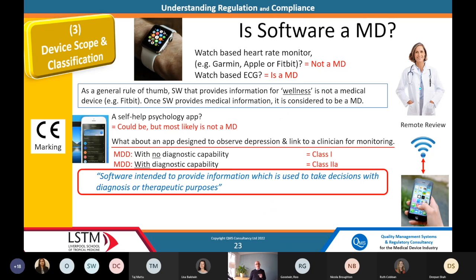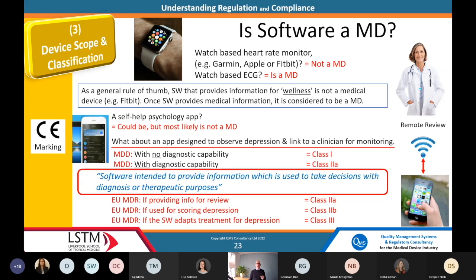Because of this new definition in the regulation, software intended to provide information which is used to take decisions with diagnosis or therapeutic purposes. Under the EU MDR, then software that was observing depression would be a Class 2A if it was being used for reviewing the depression. If it was being used to score the depression, then it would be a Class 2B. And if it was being used to adapt the treatment of that depression, it would be a Class 3.